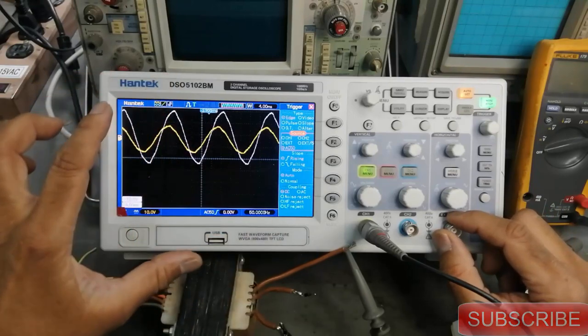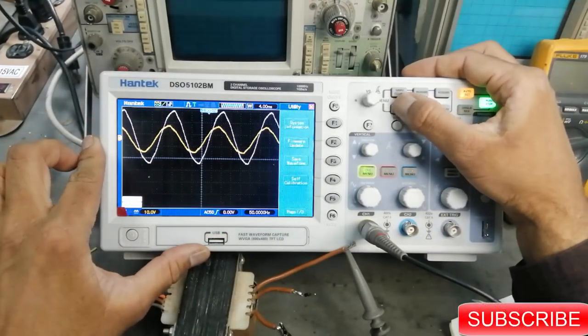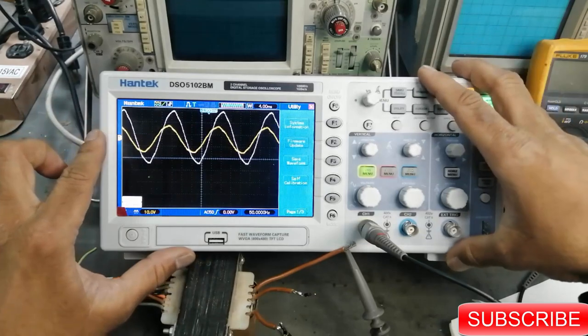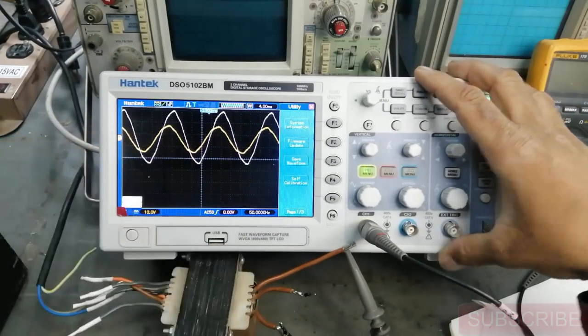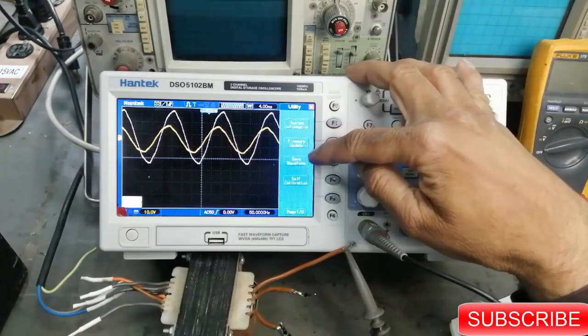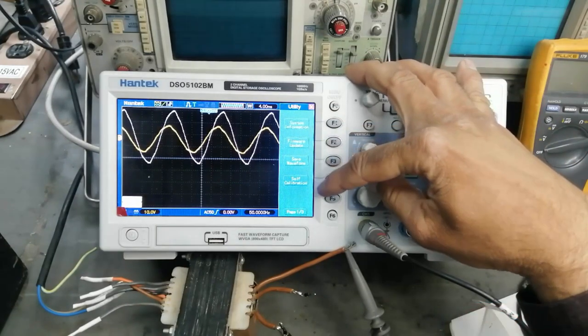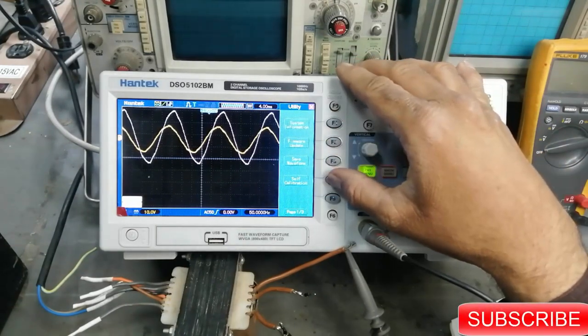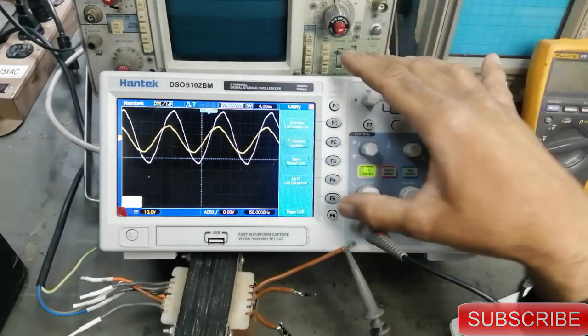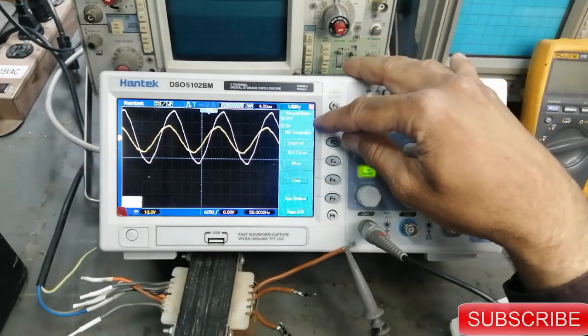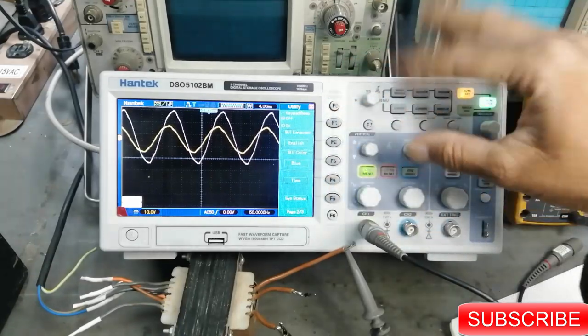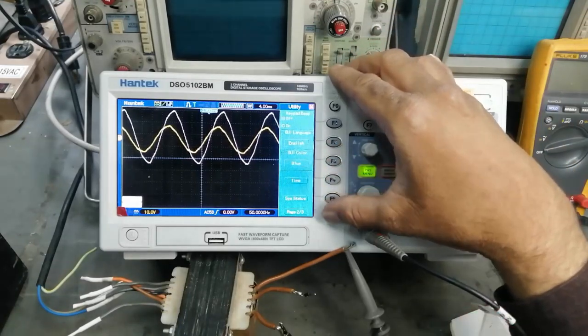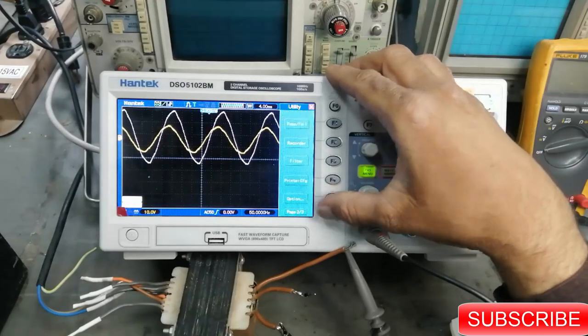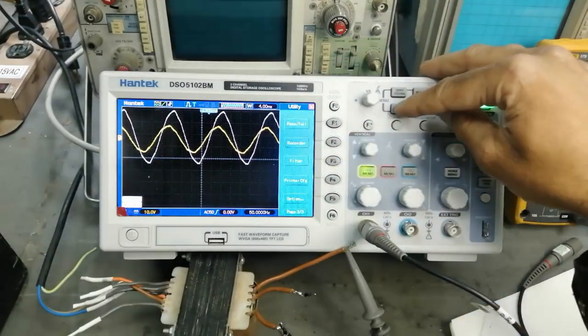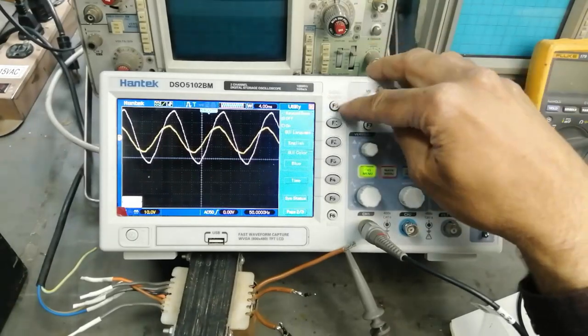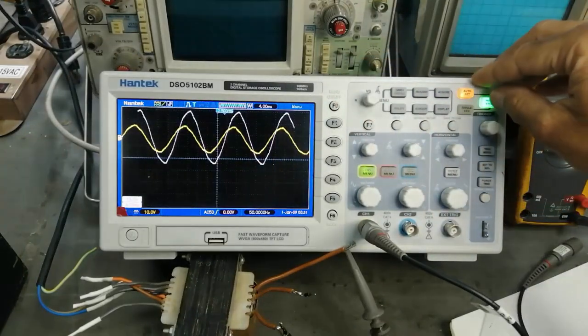Then we have utility, which is for the oscilloscope itself: system information, firmware updates, save waveform, and self-calibration. Put it to self-calibration, it will calibrate automatically. Then we have different keypad beeps and settings, UI colors and time, system defaults, system status, and everything is here. So utility is here, F0, it's off.